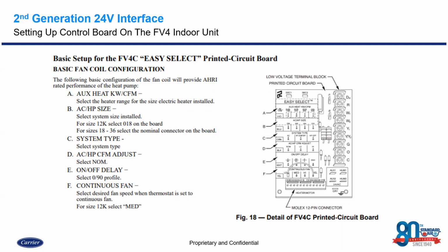do have that option. Our continuous fan speed on here, and this is the biggest thing that customers and also technicians seem to forget on here, is that these do operate just like any other ductless system where the fan will continuously run, unlike a traditional furnace where the fan comes on when the call is active and it shuts off usually a couple minutes after the call has went away. So these fans will continuously run.